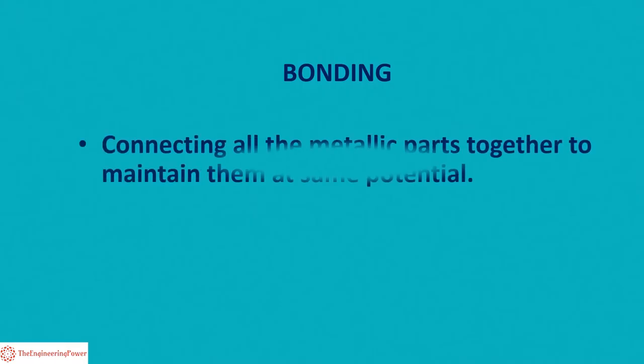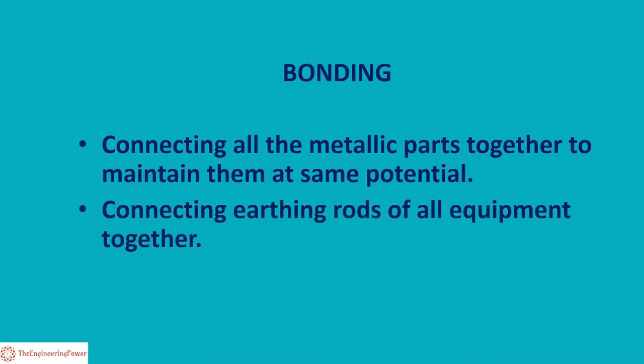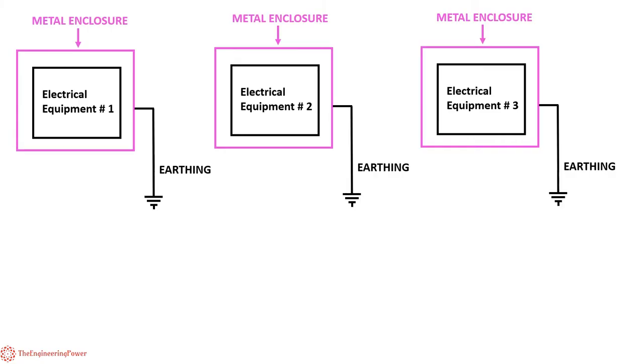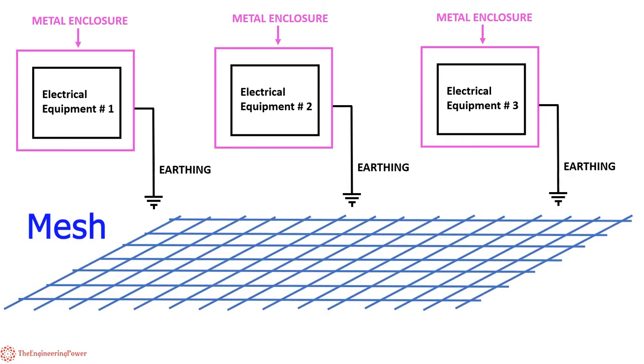By bonding we mean to connect all the metallic parts in the work area together to maintain them at same potential, that is ground potential. Basically, we are connecting the earthing rods of all the equipment together. We achieve this by installing a mesh in the work area, for example the yard in a substation, and connecting the earth rods of all the equipment to the mesh, thereby achieving equipotential between all the equipment. The mesh is generally referred to as the earth mat or ground mat.